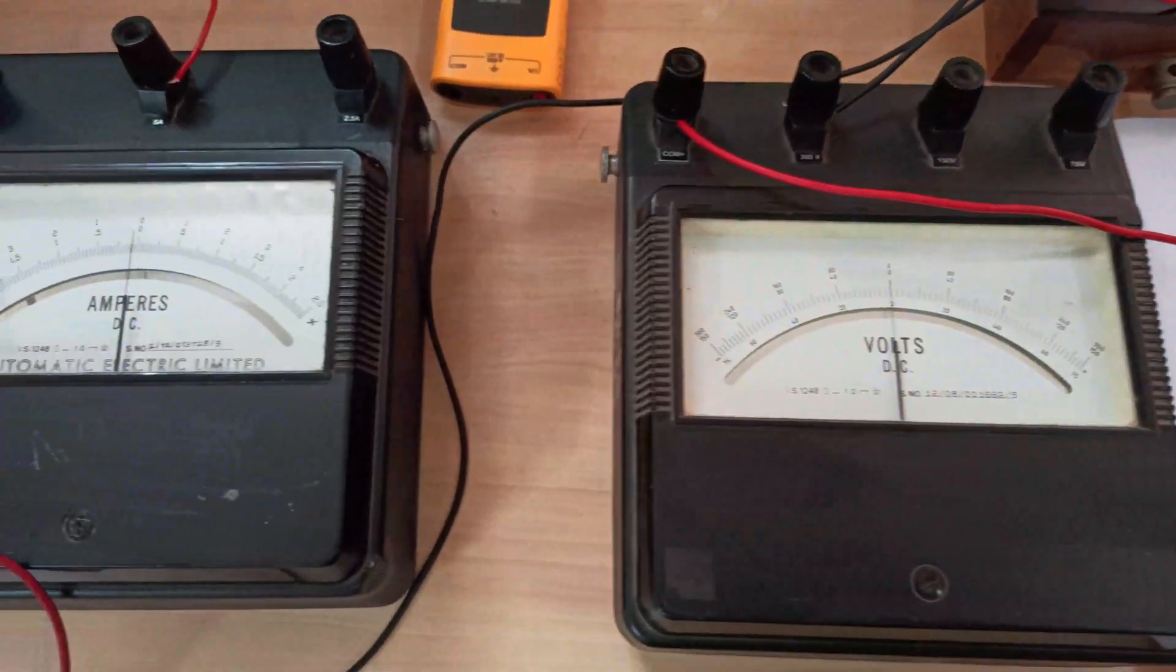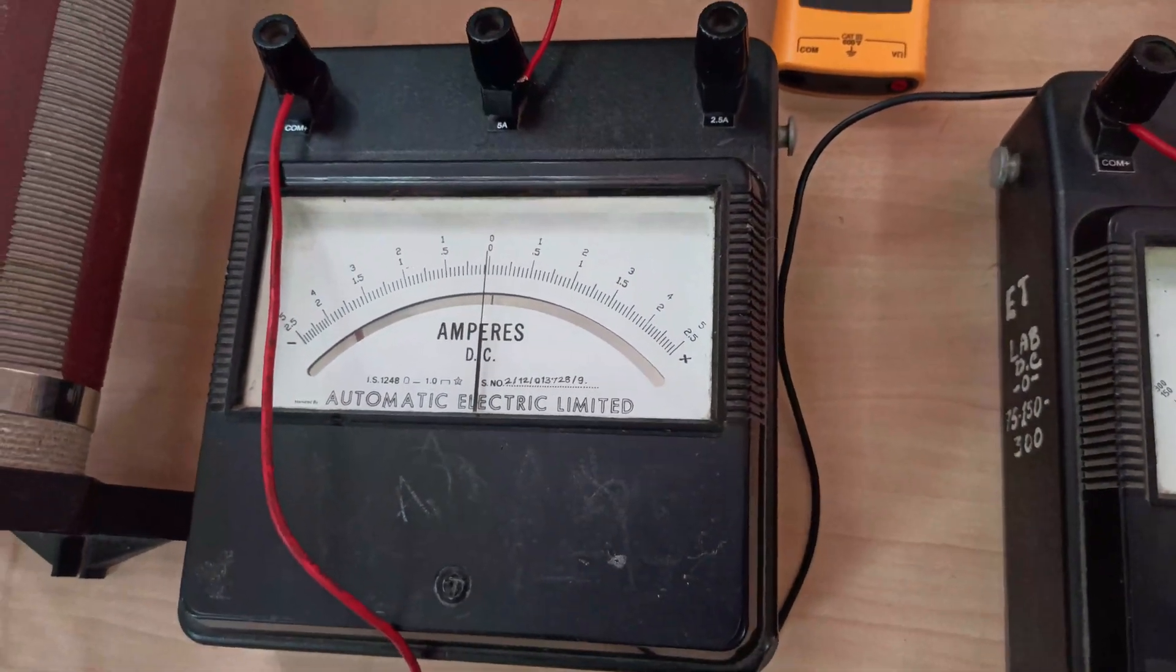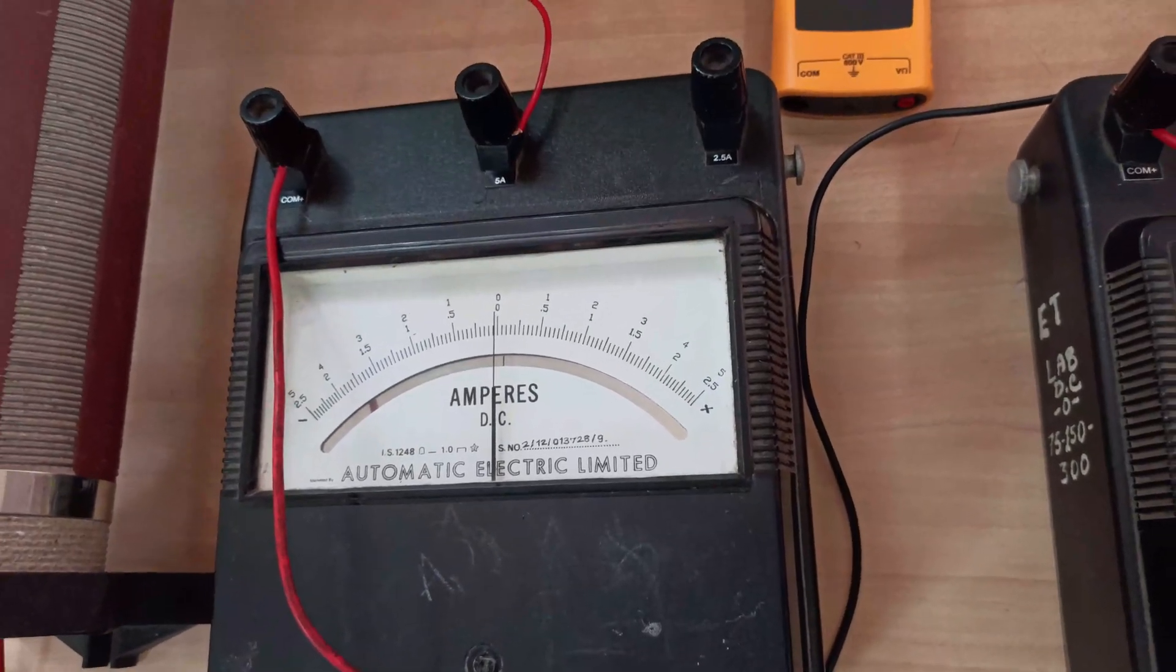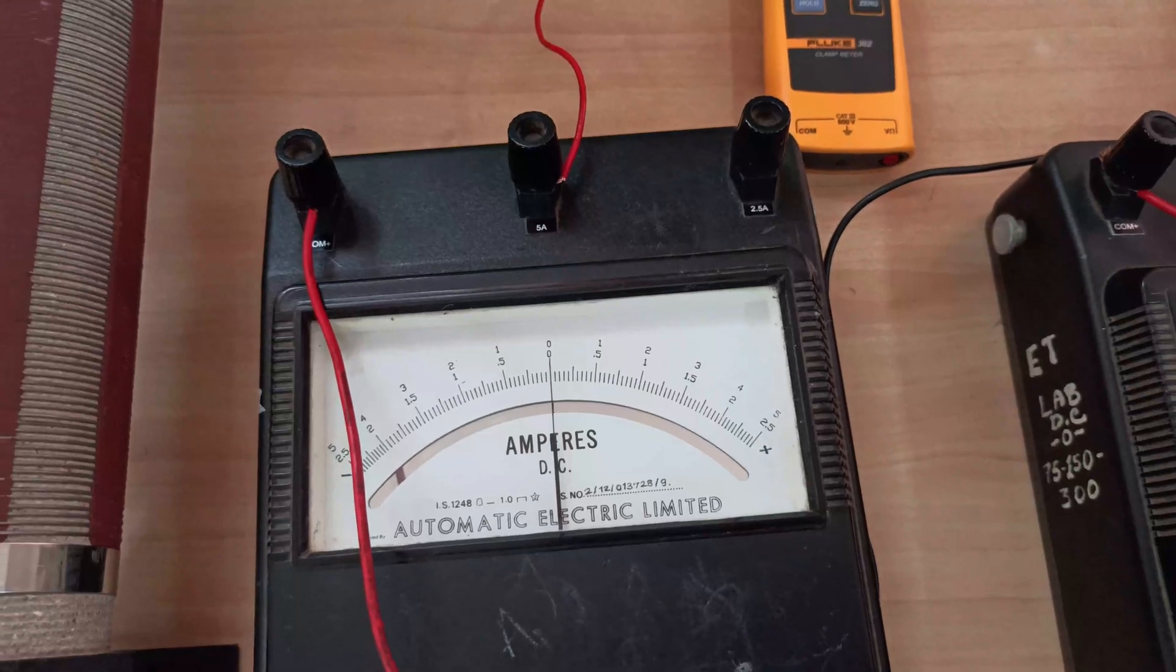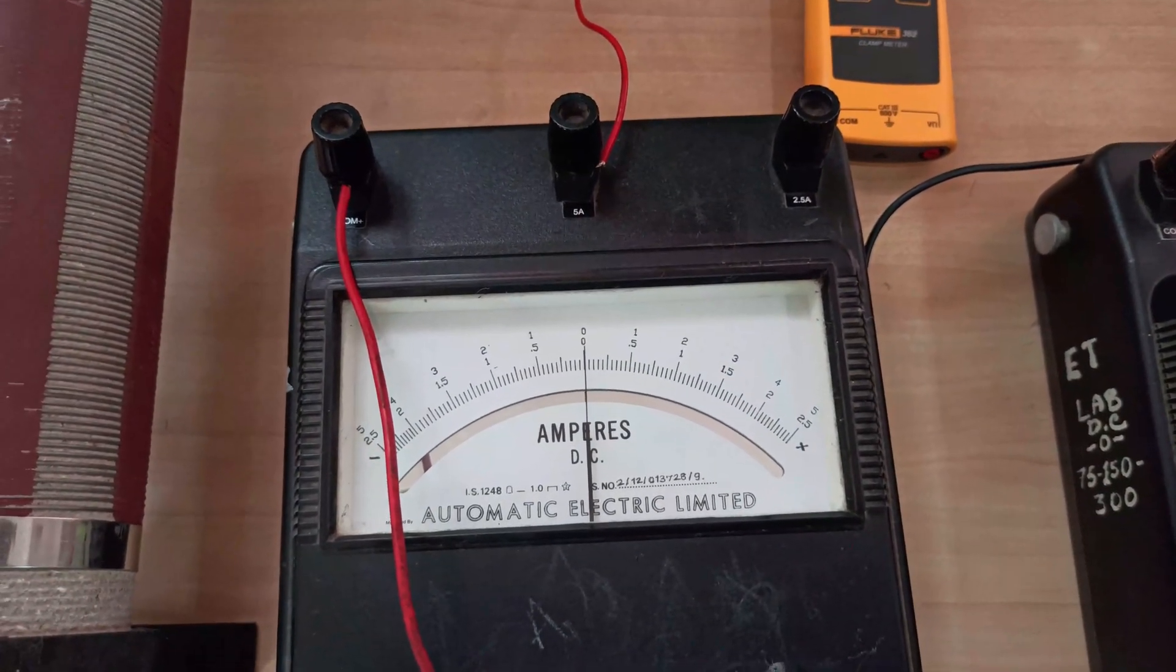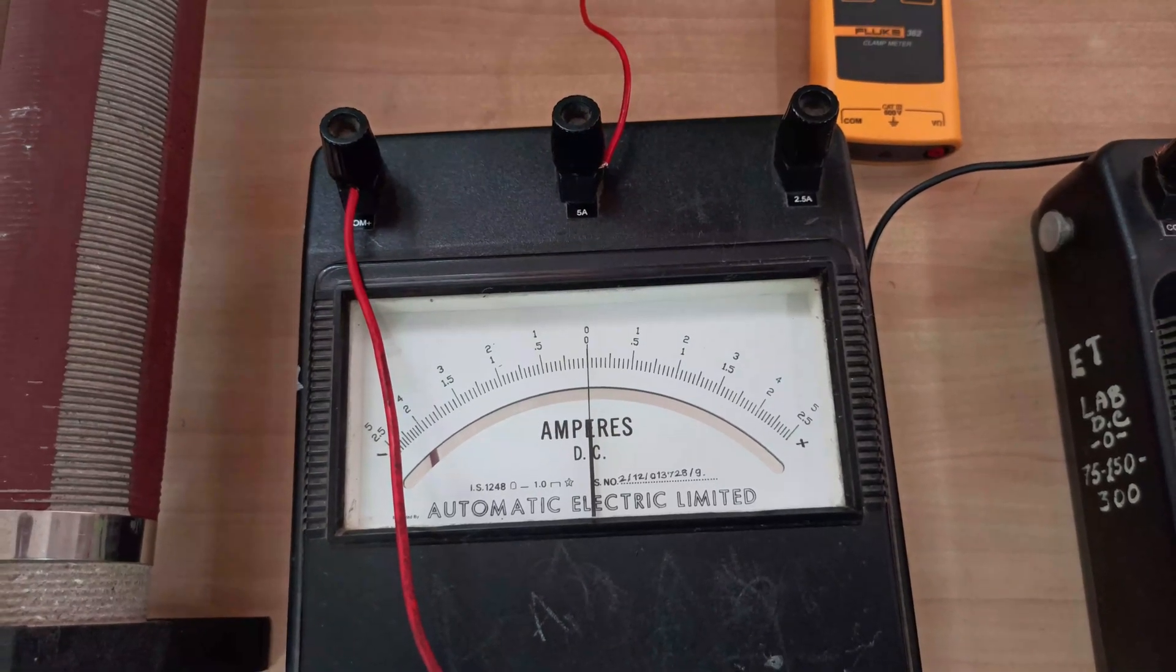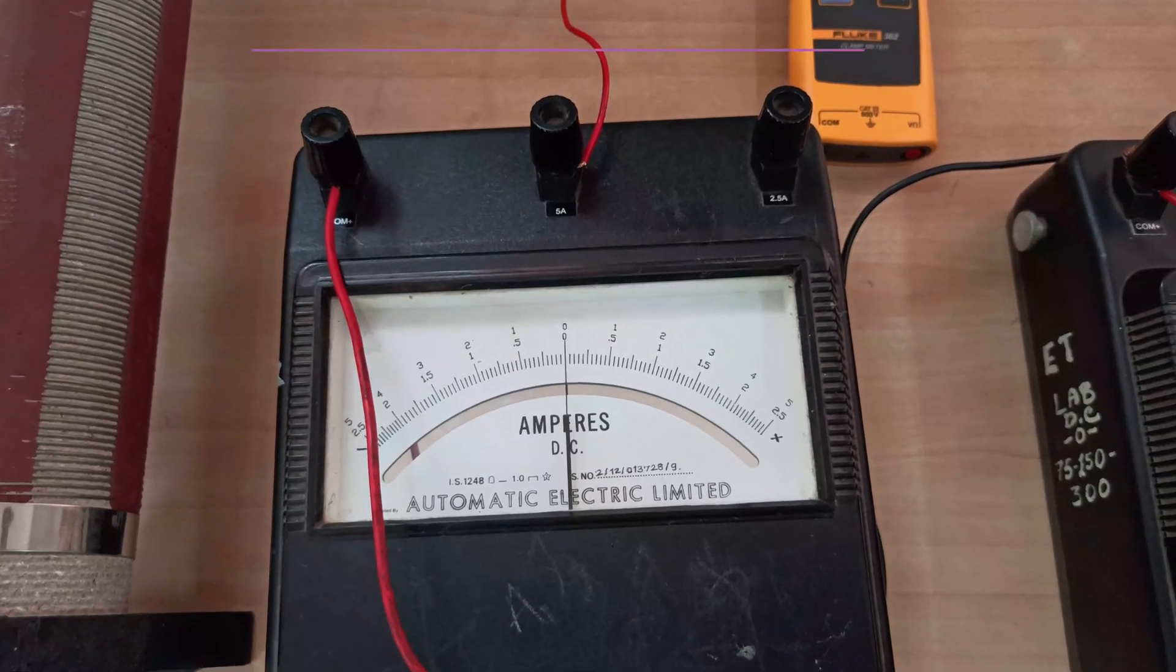The same thing goes with the ammeter. Here again you can see the actual indicator and its mirror image are not aligned. So again you position yourself such that those two lines are seen as a single line. Here you can see that indicator is perfectly aligned with the zero, so you need not do any offset adjustment. It is perfectly fine.